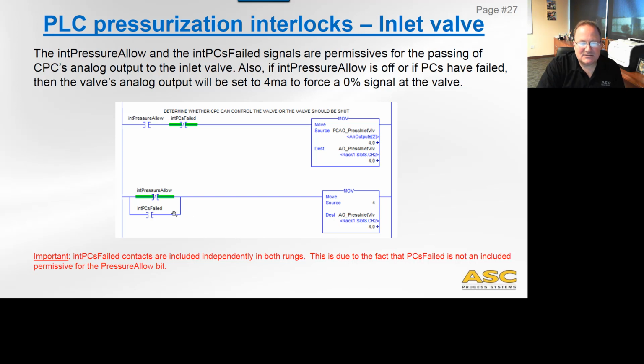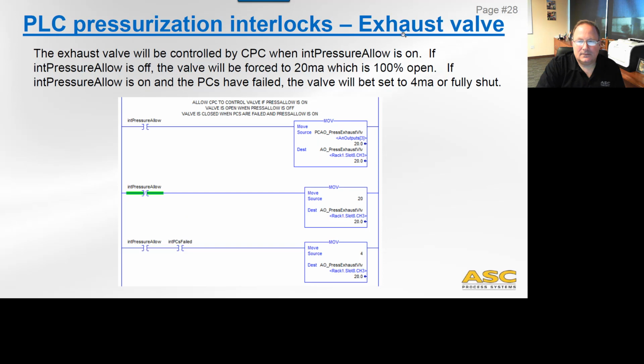And so this is basically saying, hey, if I either don't have pressure allow or I have PCs failed, I'm going to move the 4 over to the valve and shut it. Exhaust valve works a little bit different. If I'm allowing pressure control, I'm going to move CPC's exhaust valve command to the valve. If I don't have pressure allow, then I'm moving a 20 to the exhaust valve, wide open. If I'm allowing pressure control, but my PCs have failed, I'm going to move a 4.